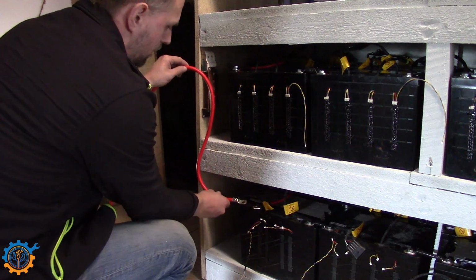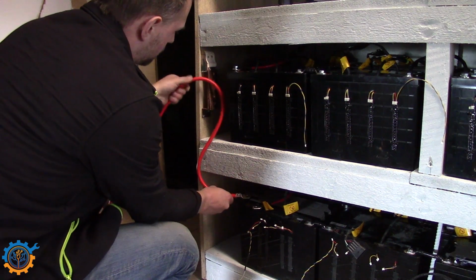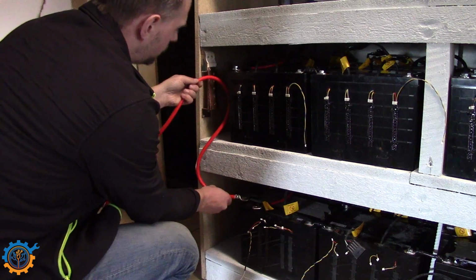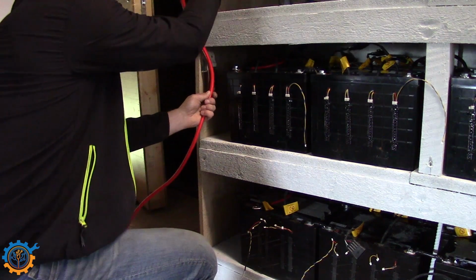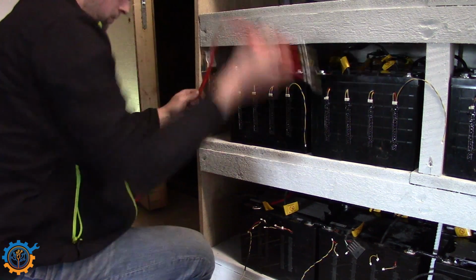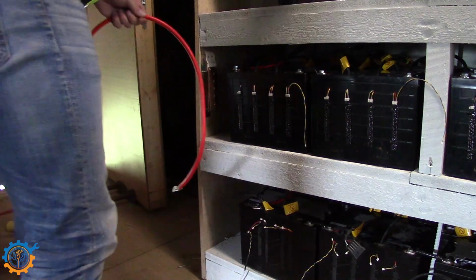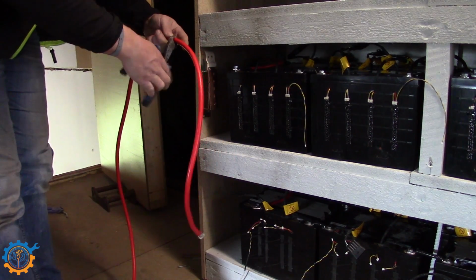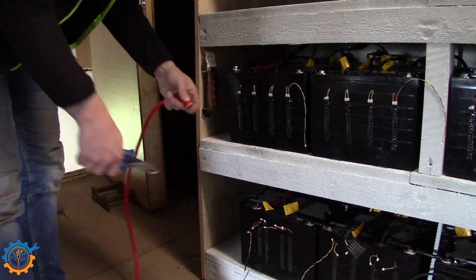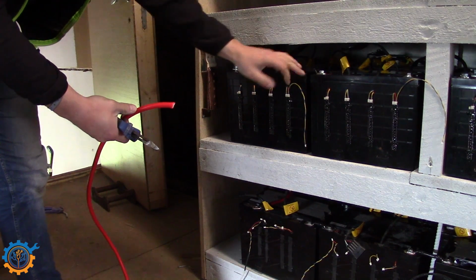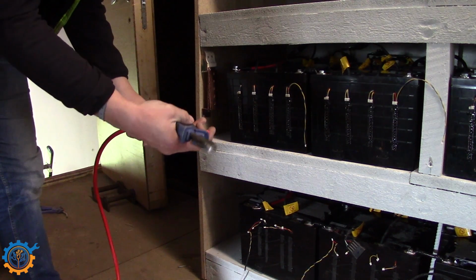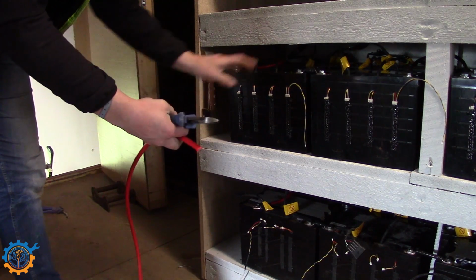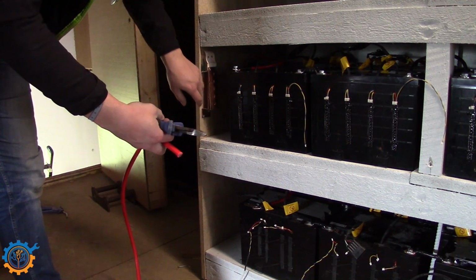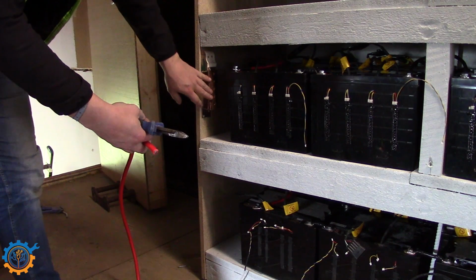I'm going to measure out now how long the cables need to be here. That should be fine, because then I can use it both on the top and the bottom. Then it's just a matter of cutting the cables - I'm using 16 square millimeter between the batteries, 25 square millimeter from the strings to this terminal, and 50 millimeter from this terminal down to the inverter.